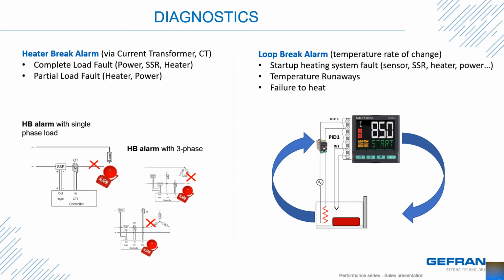There are many good applications for loop break alarm. I've seen it firsthand in IR heating where the temperature sensor was misaligned with the heating target. On extruders, because of the time to heat, they tend to be turned on and walked away as they heat. With the thermocouple sometimes not seated properly in the well, or maybe it's laying on the floor of the plant. Either way, in those cases, the heats could turn on, not see a rate of rise, and the heats could just run away and we could start melting down the heaters.